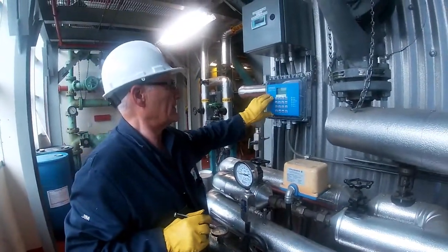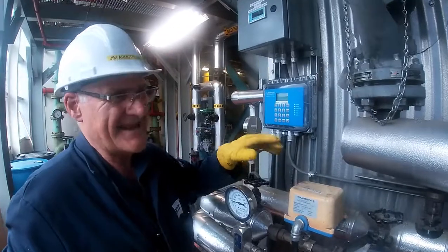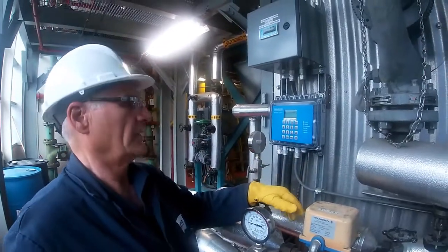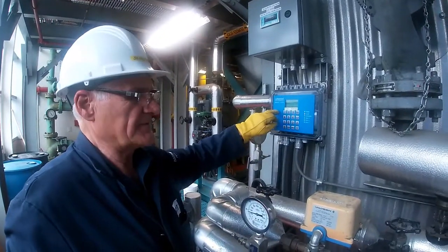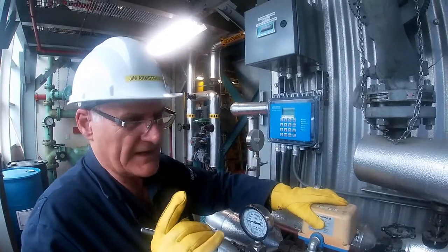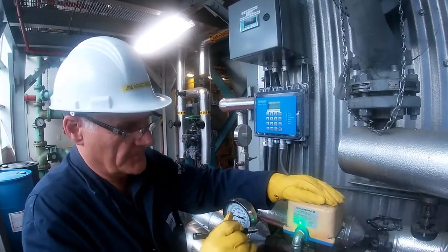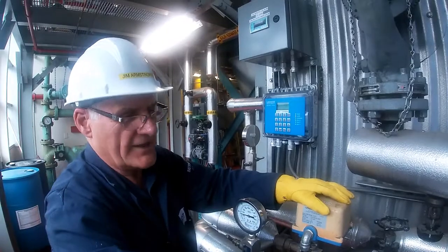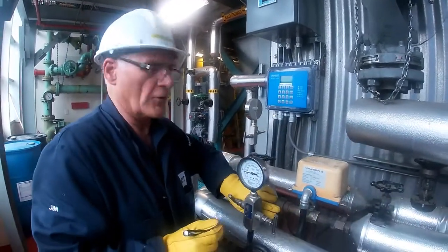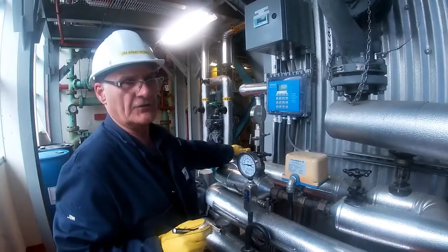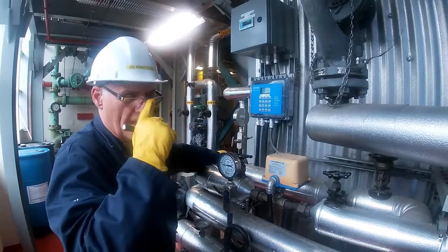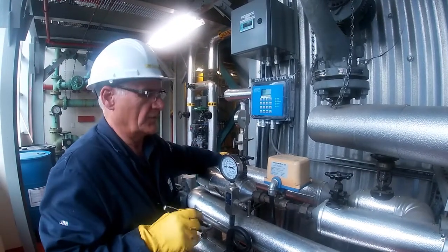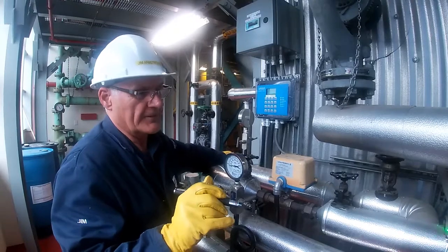The blowdown controller itself is a sample cycle type of controller. What happens is that once every 30 minutes, it opens this valve. Okay, so this valve opens, and you start to get a flow coming through that orifice, and then heading down to the blowdown down below to a condensate separator.